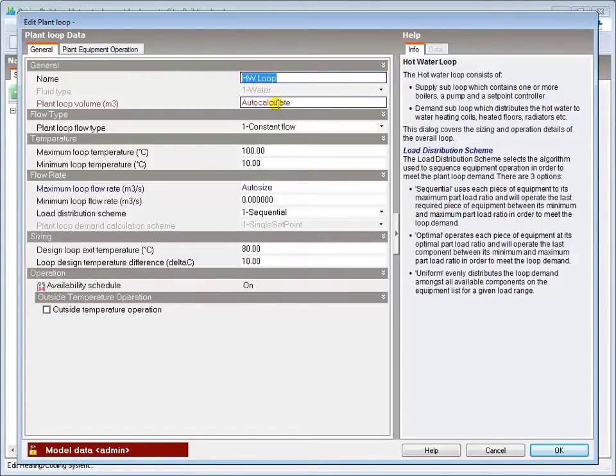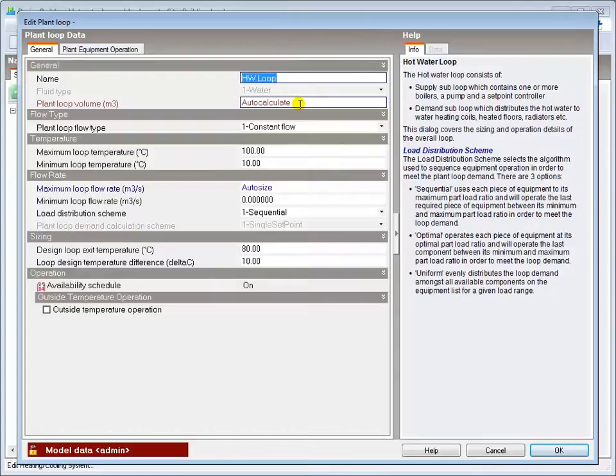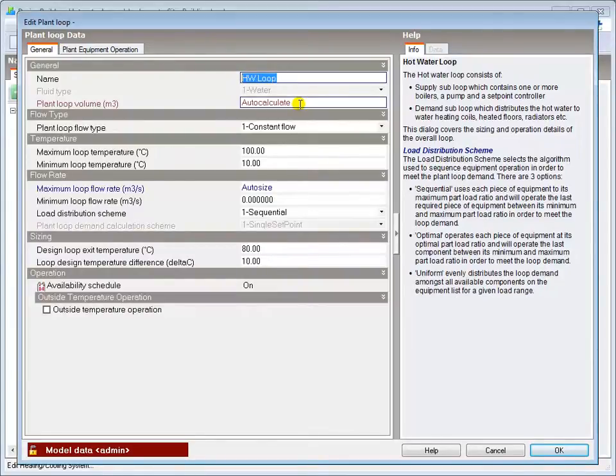The plant loop volume determines the capacitance of the system, which ultimately affects the system response time to control actions. If you don't have data for the whole loop volume, the auto-calculate option gives reasonable results for most system sizes.